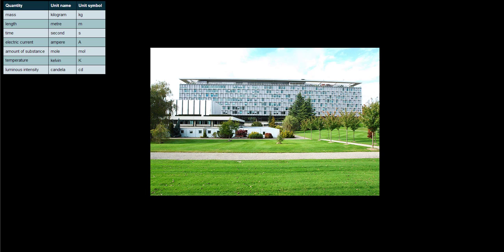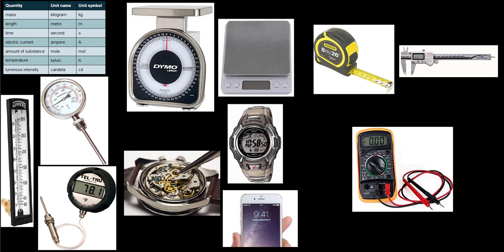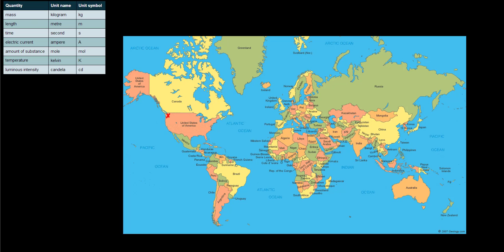So for any measuring device, you will be able to trace the references used to produce that device to one worldwide accepted master reference. So for example, a guy making a tape measure in Seattle versus a guy making a tape measure in Asia, if both tape measures are made in English units of feet and inches, then if you follow the references for each instrument through the different agencies like we just described, you will converge at a point, that point being the worldwide accepted master reference for length.